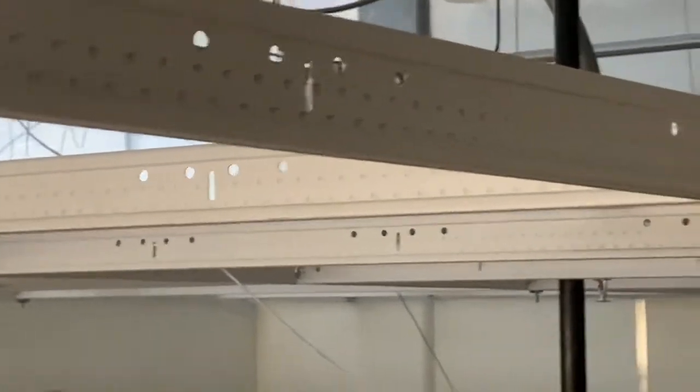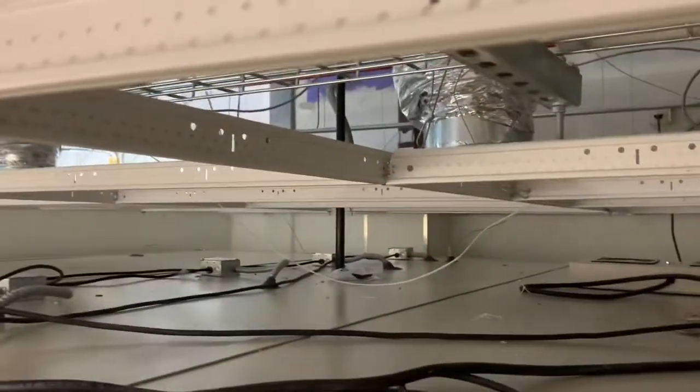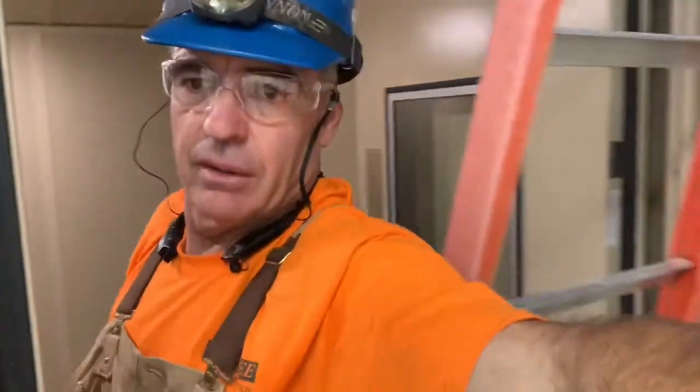I could lower it just a little bit, maybe. But here's the star of the show — this concealer head. This is what we call a concealer head. Look at how flush and pretty that is. In a sound booth you have a low ceiling, probably seven foot six or seven, so you use the concealer. That should — no, that WILL put out a fire in here.